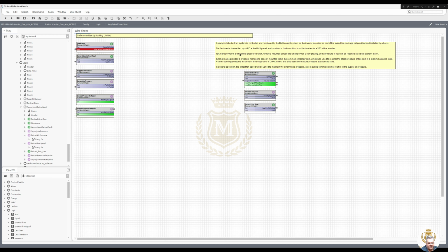The fan inverter is enabled by a fault free contact from the inverter. Okay, so we need this one to be true, or the opposite anyway to that at the moment, and that's false. I believe healthy is false. So if it goes true, then there's a problem. So let's put a NOT gate on the fault. Invert fault. So that's now a true. If that was all working, that would be a true.